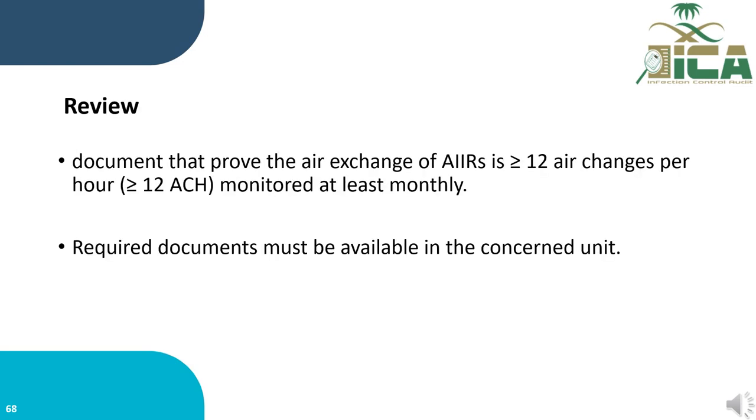Review all documents that prove the air change of the airborne infection isolation room is 12 or more air changes per hour, and that it is monitored at least monthly. All of these documents should be available in the unit when you visit any isolation room in any department. It should have a copy inside this department.